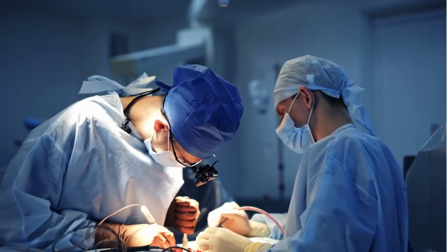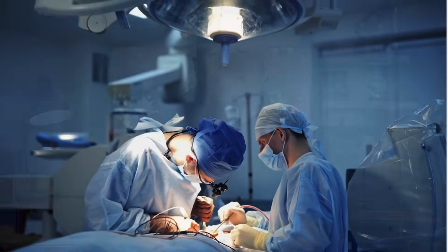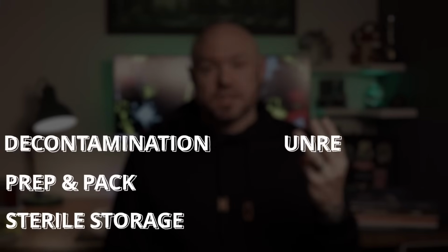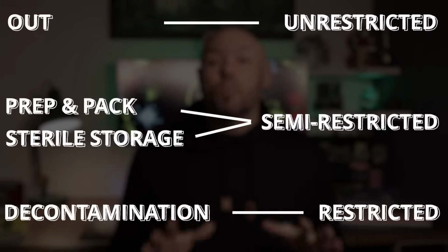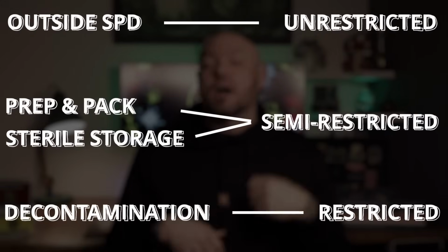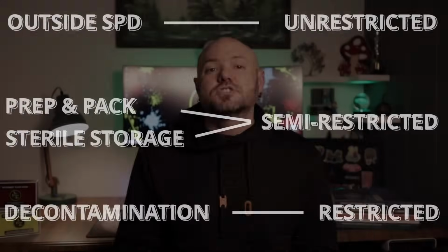And lastly, restricted level refers to the areas where procedures or surgeries actually occur, or a very biohazardous area. In these areas, you would be wearing a whole lot more protective attire over the items we already discussed. You'll find restricted level inside the operating rooms themselves, where surgery is in progress, as well as decontamination where it's very biohazardous. But for sterile processing in general, think semi-restricted. Okay, I hope you're still with me. Three physical areas of sterile processing: decontamination, prep and pack, and sterile storage. And then three risk levels, which determine the level of clothing and protective attire to be worn in each area depending on that area's risk level: unrestricted, semi-restricted, and restricted. These risk levels set the standards for what attire should look like by each area of the department.